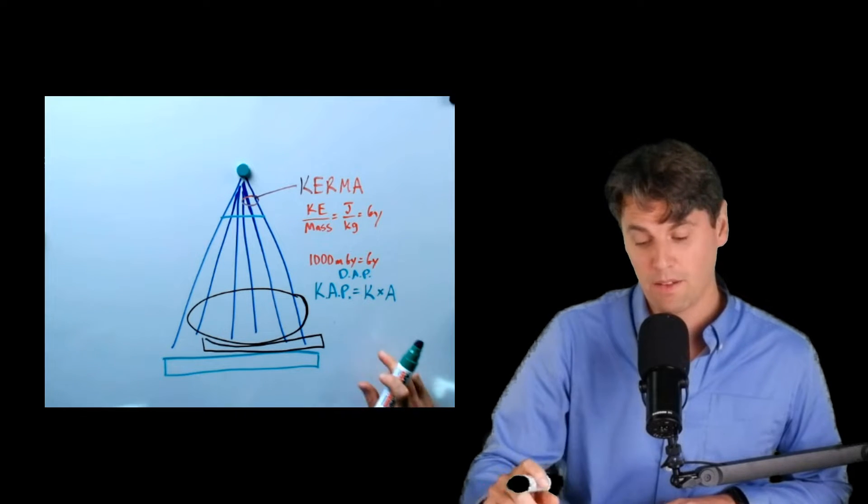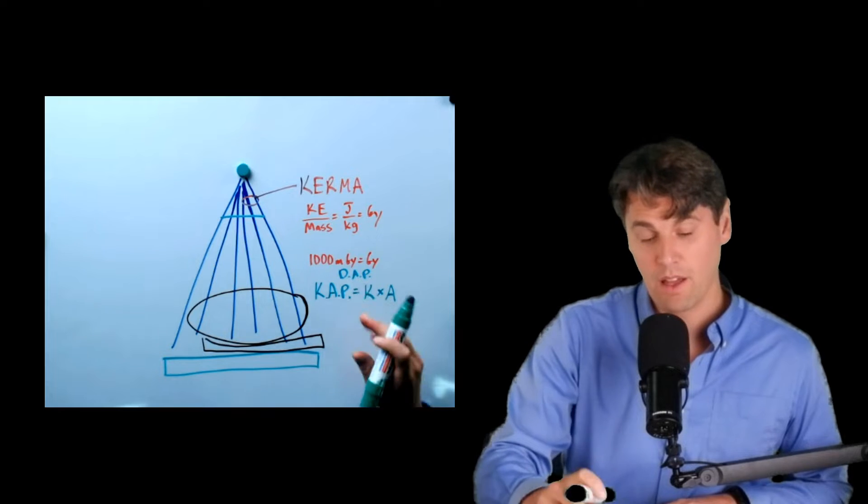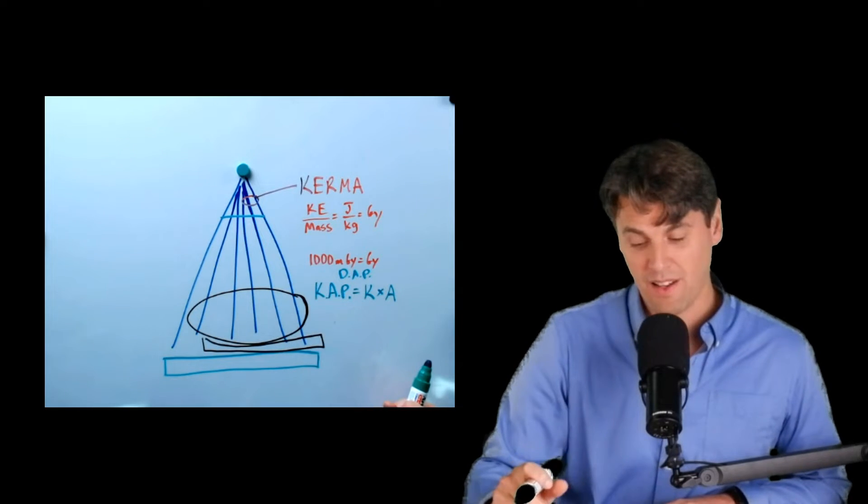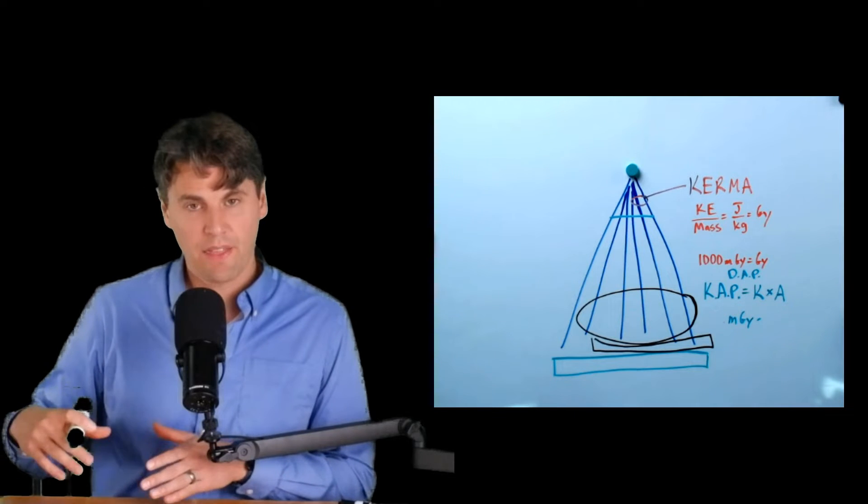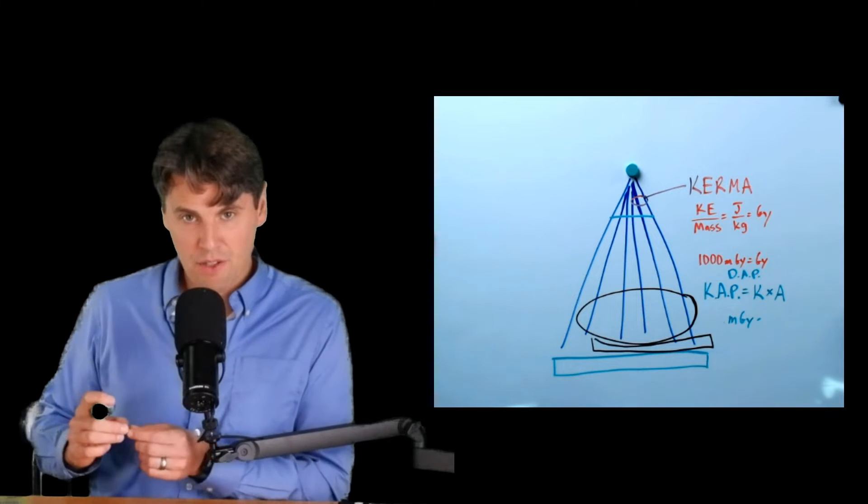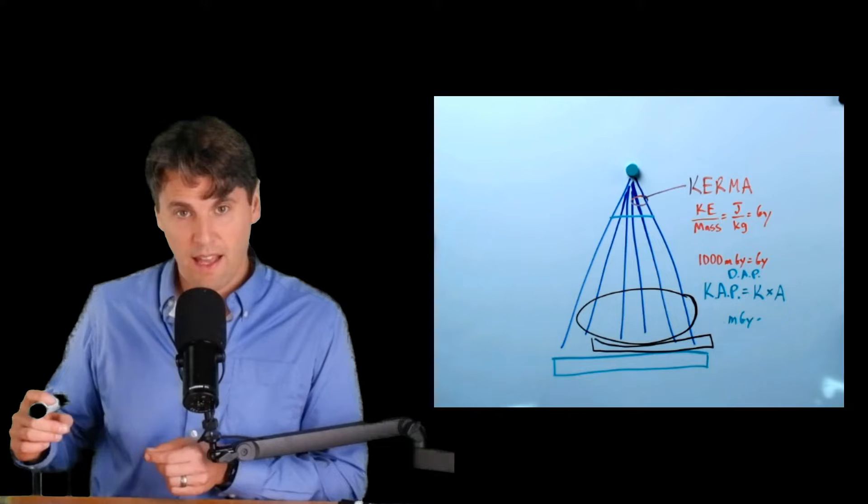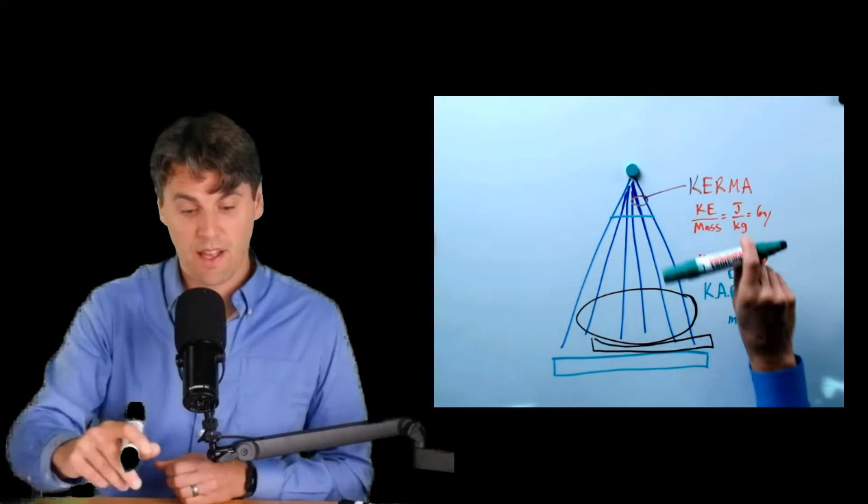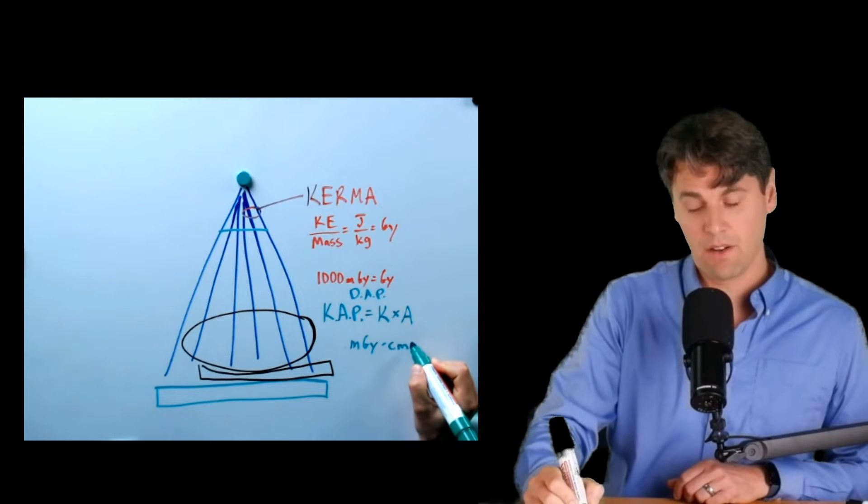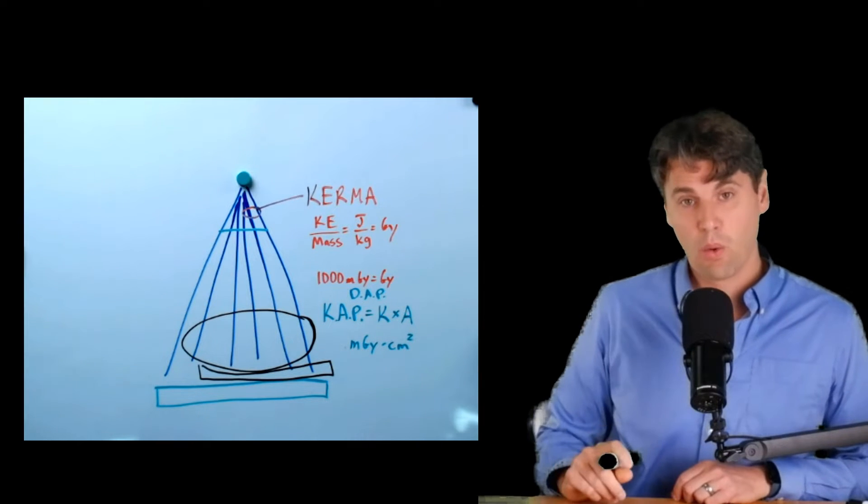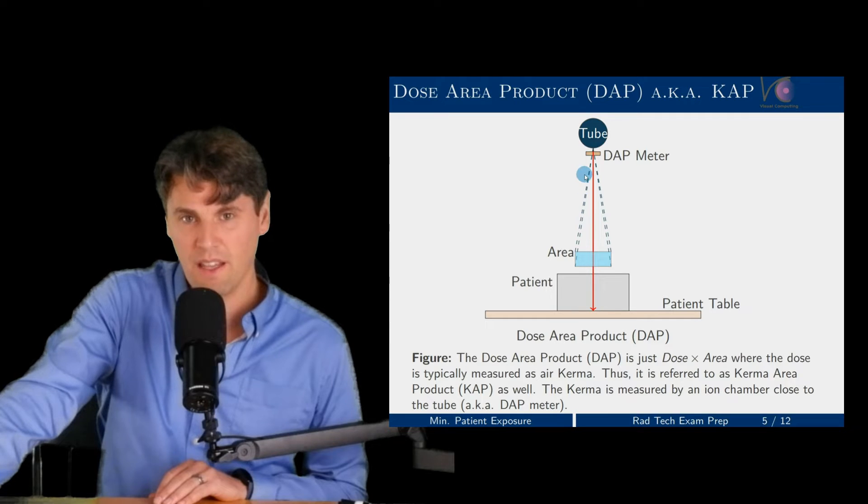This is also called the dose area product, because Kerma is just a unit for the dose that's measured in air. If we have a little rectangular area, we can think about that as being measured in centimeters on one side by centimeters on the other side for the area that the x-rays are going to be irradiated. We're going to have centimeters multiplied by centimeters or centimeters squared. You can see here we have our tube. We have a dose area product meter. Then you can see the beam that is actually irradiating the patient here.